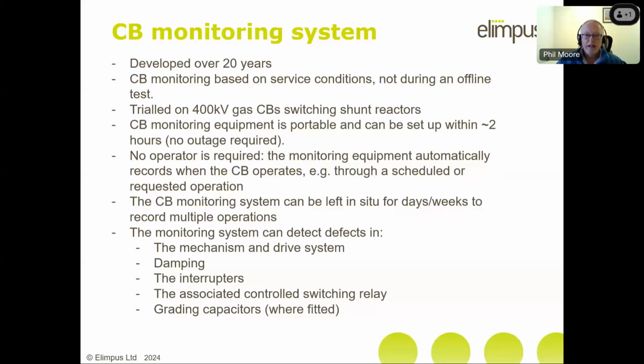The circuit breaker monitoring system is based upon service conditions. It's not an offline test. If the circuit breaker is out of service, this system won't work at all. It needs the system to be in service to produce any useful results. We've trialled it entirely on 400 kV gas circuit breakers using switch shunt reactors. We've actually started doing other tests now on other applications than shunt reactors, but it's shunt reactors where it has potentially the most benefit as we speak.